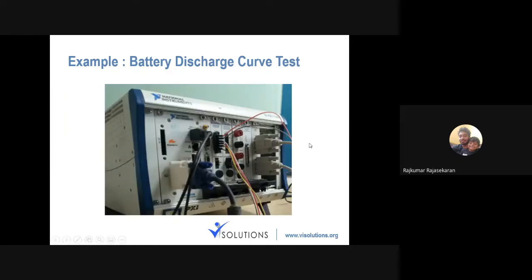It's not like we used DAQ there. Instead of this small hardware, we used a specialized instrumentation-based computer called PXI, which made use of specific instruments used for battery charging and discharging testing, something called a source measurement unit. So we are connected to that. To make measurements, we also had a DMM as well, which we have not used as of now.